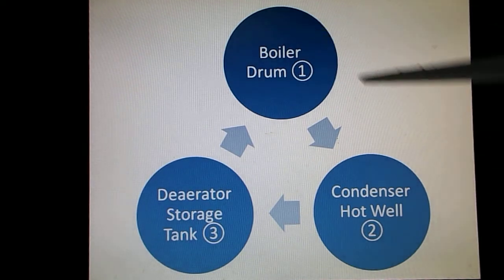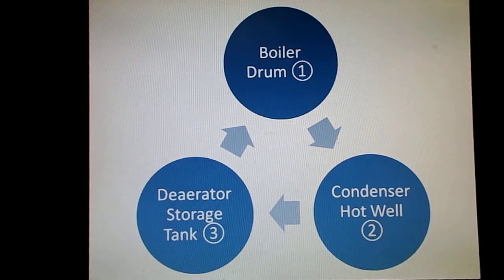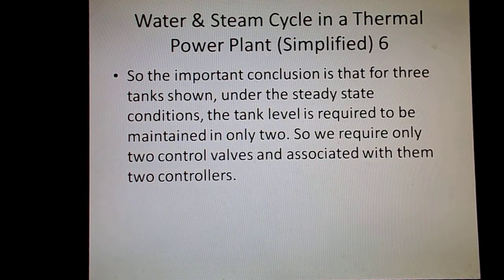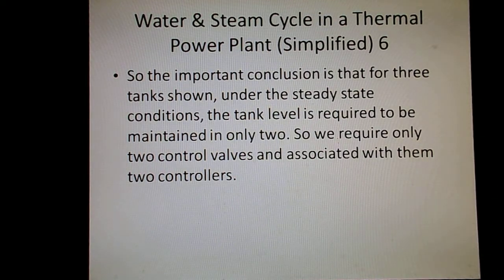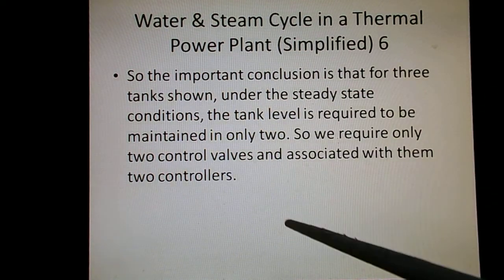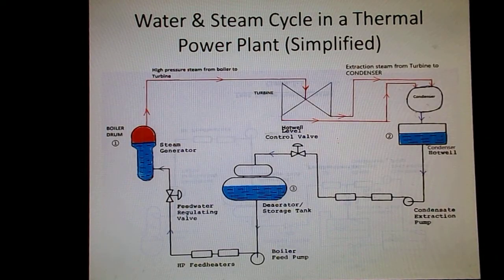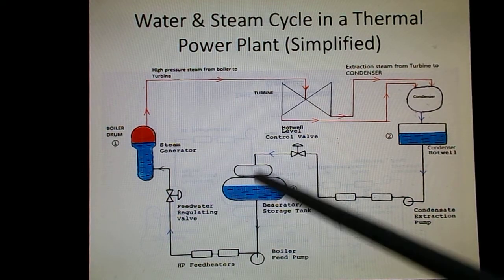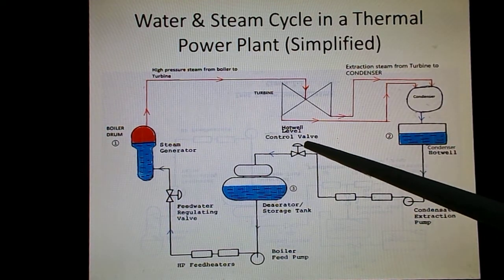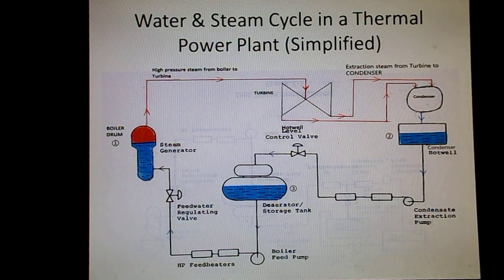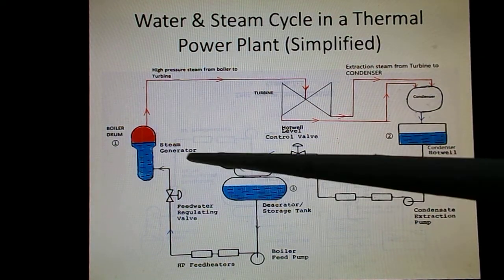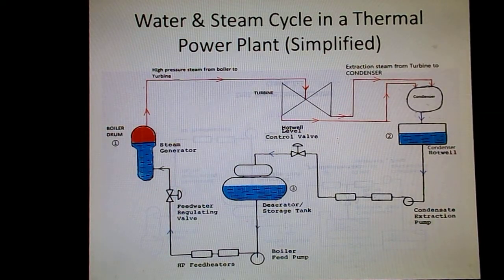As shown in the diagram, the important conclusion is that under steady state conditions, tank level needs to be maintained in only two of the three tanks. Therefore, we require only two control valves and two associated controllers. For the three tanks, we use two control valves and maintain level in two tanks.